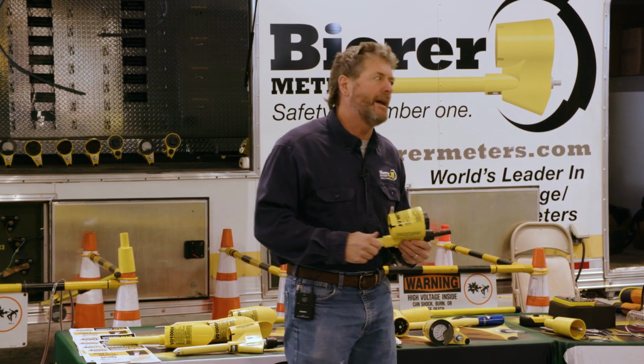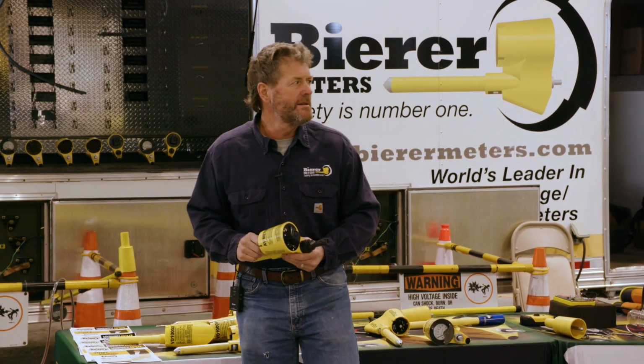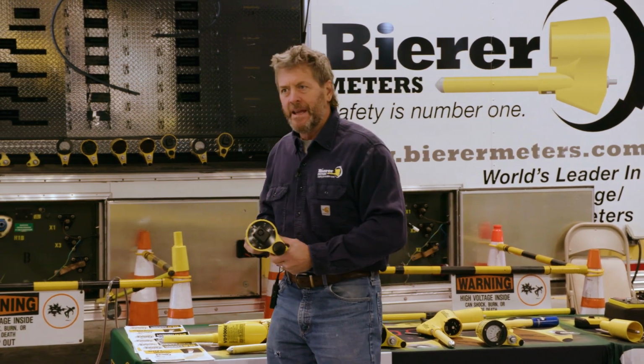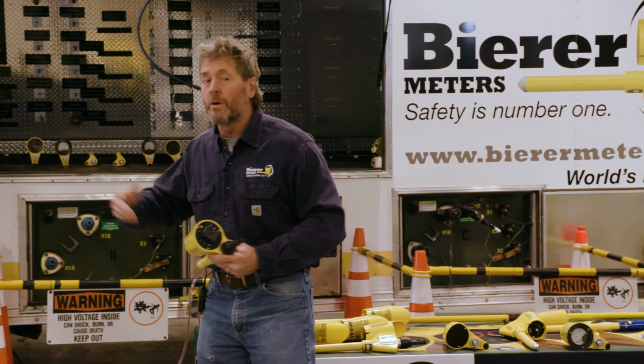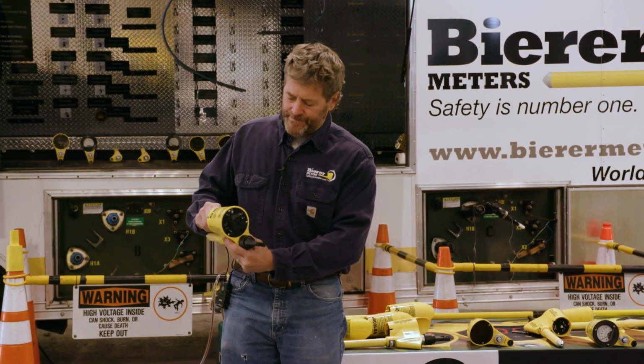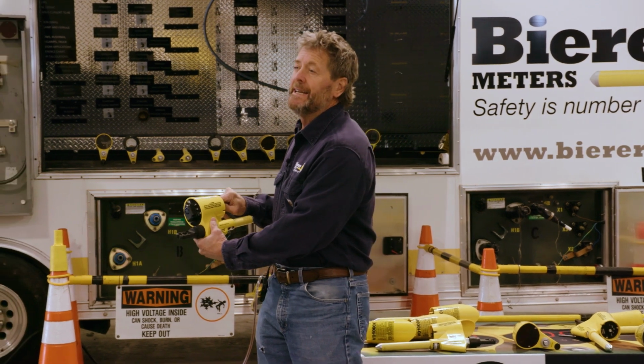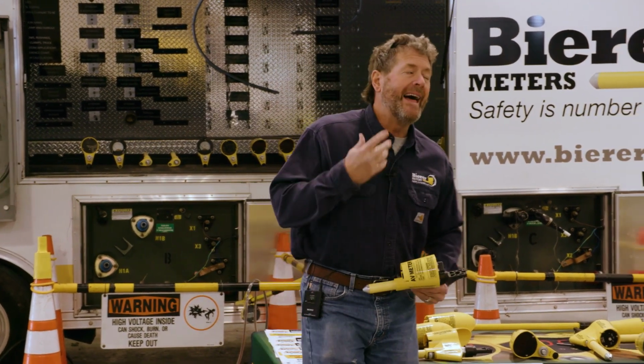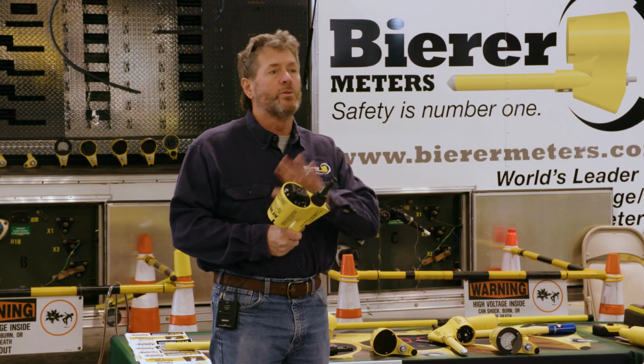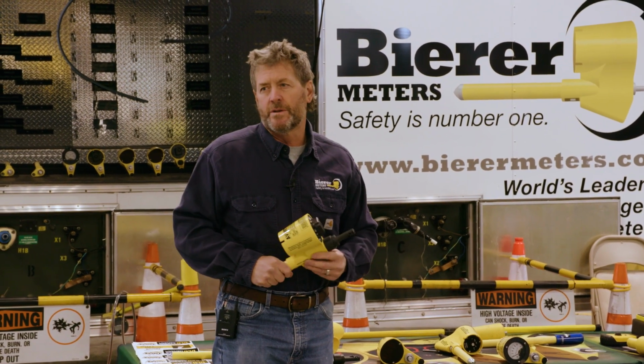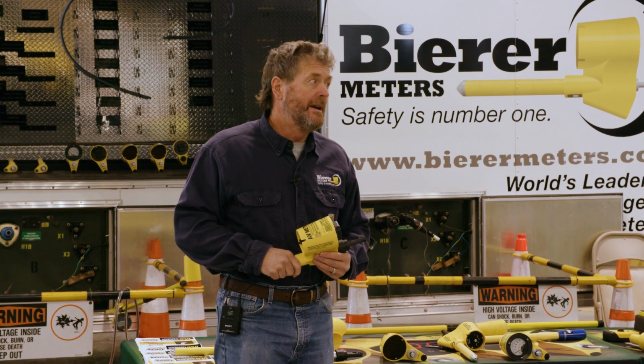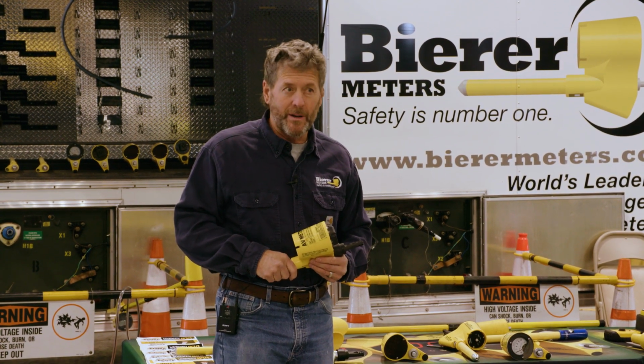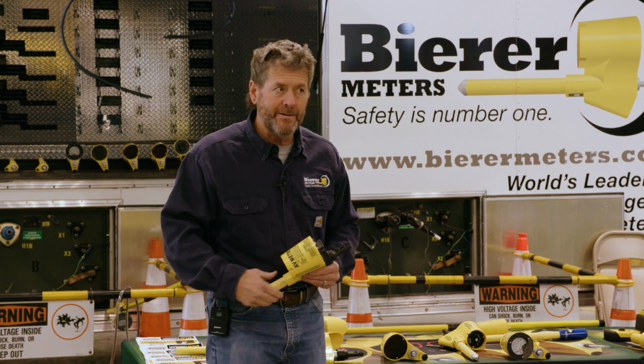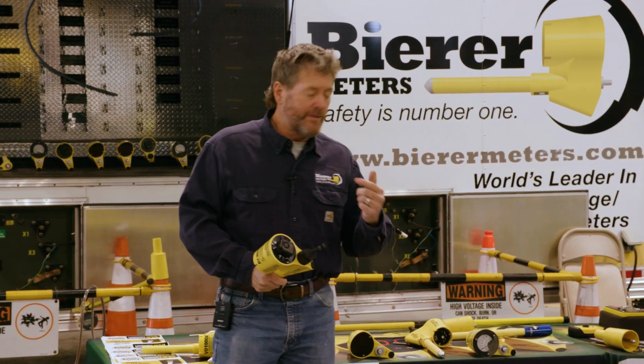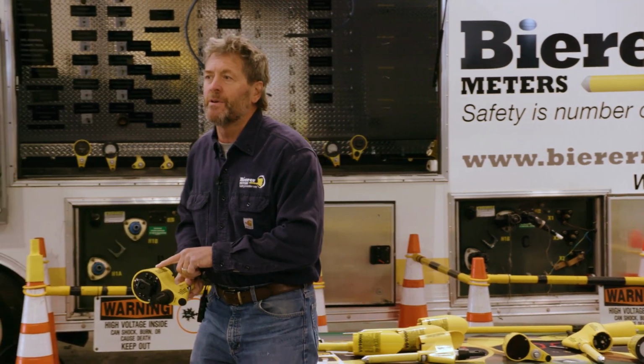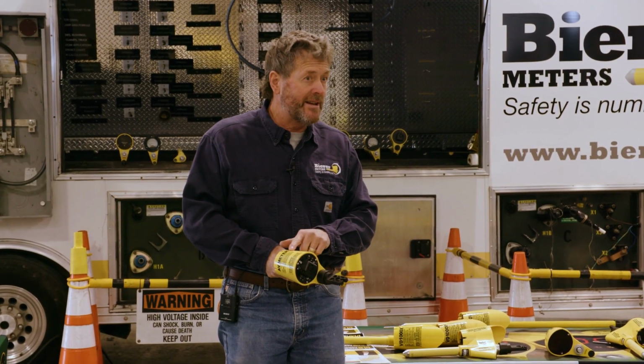If you ever use a horn and light tool, or go to a utility or contractor that does, you want to see in here. It's real simple. That only tests the battery, does not test the tool, anybody's, on a live known voltage source. It just tests the 9-volt battery. It doesn't verify your tool is functioning properly at all. It just lets you know the battery is functioning properly, and it's good. There is no transformer in here stepping up 9 volts to high voltage for a true tool functionality test.